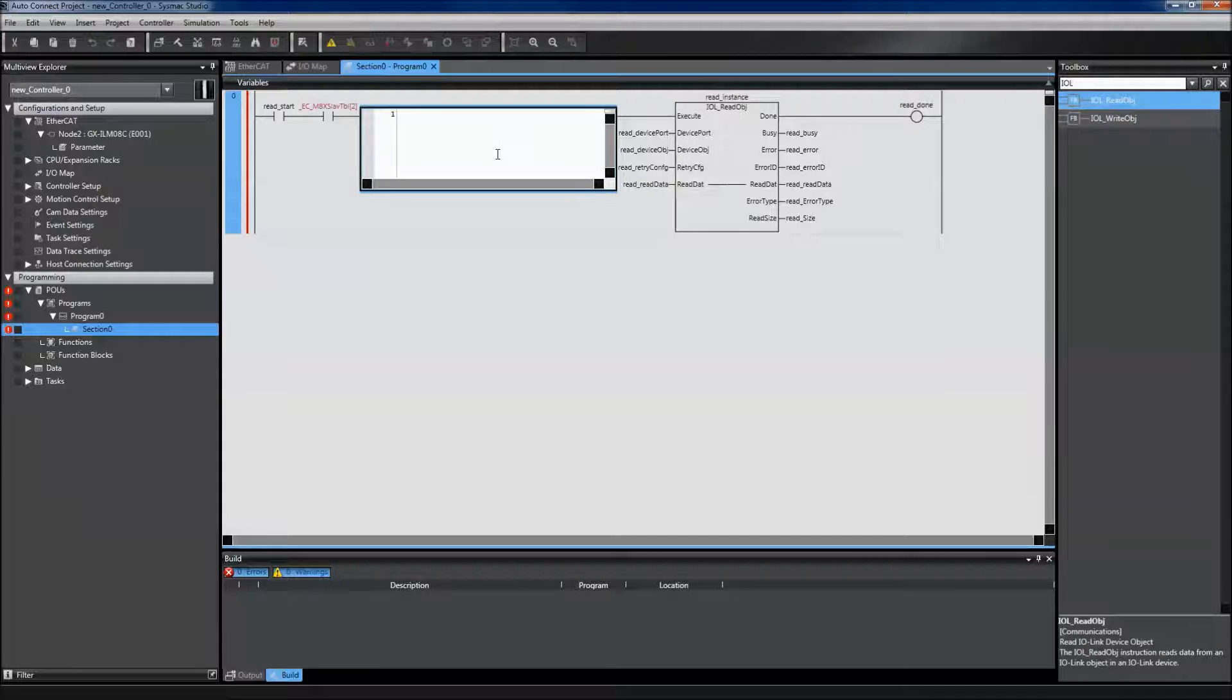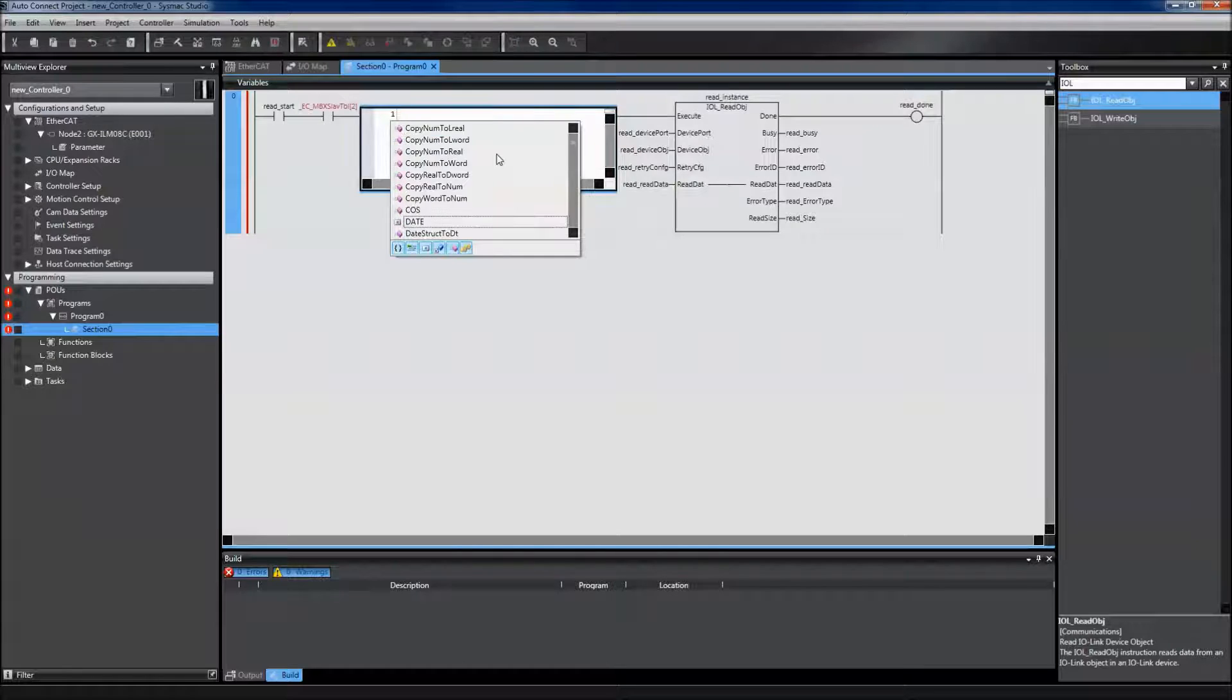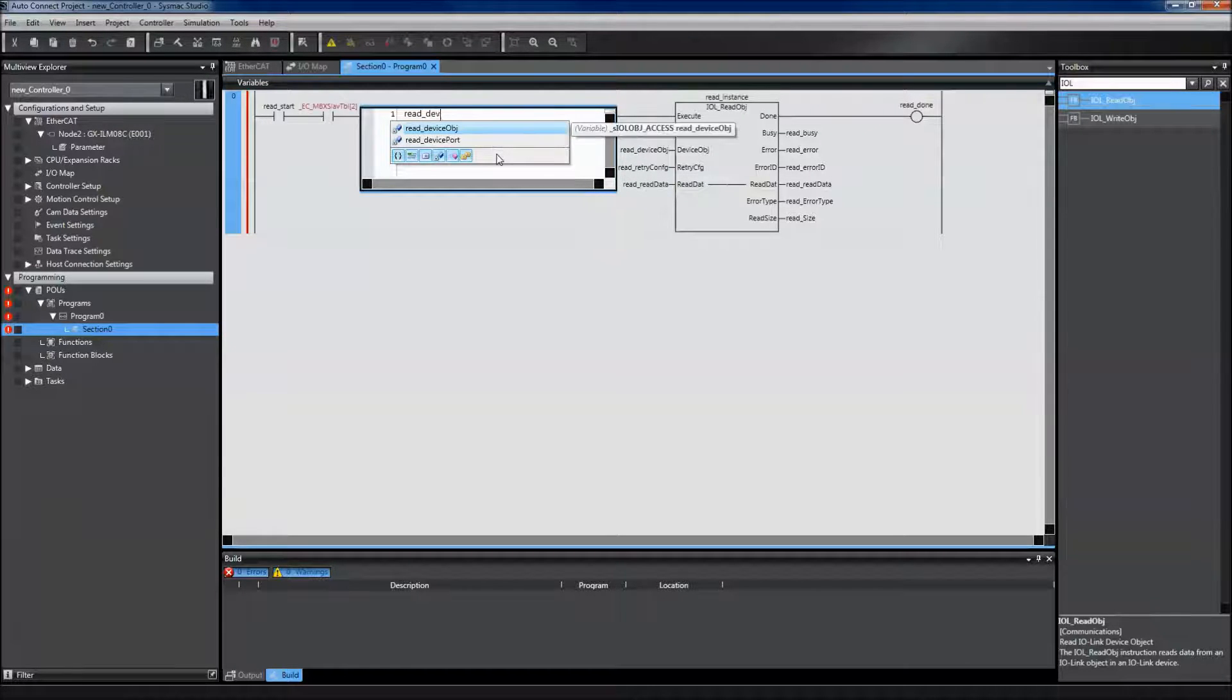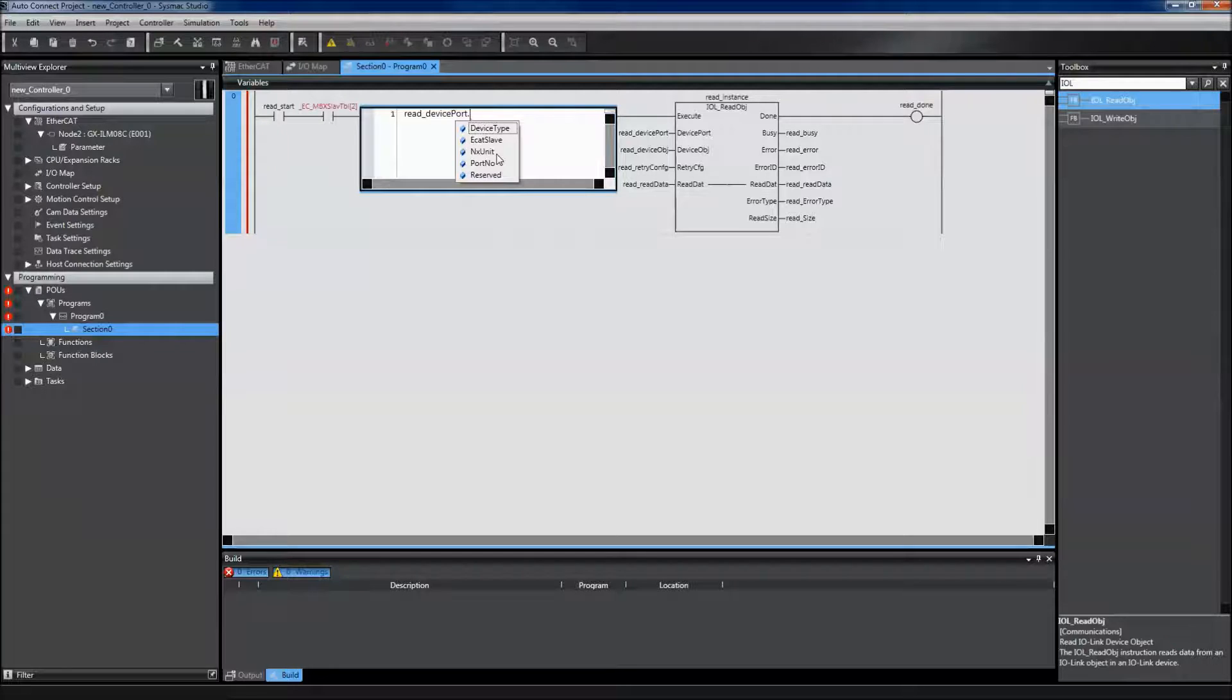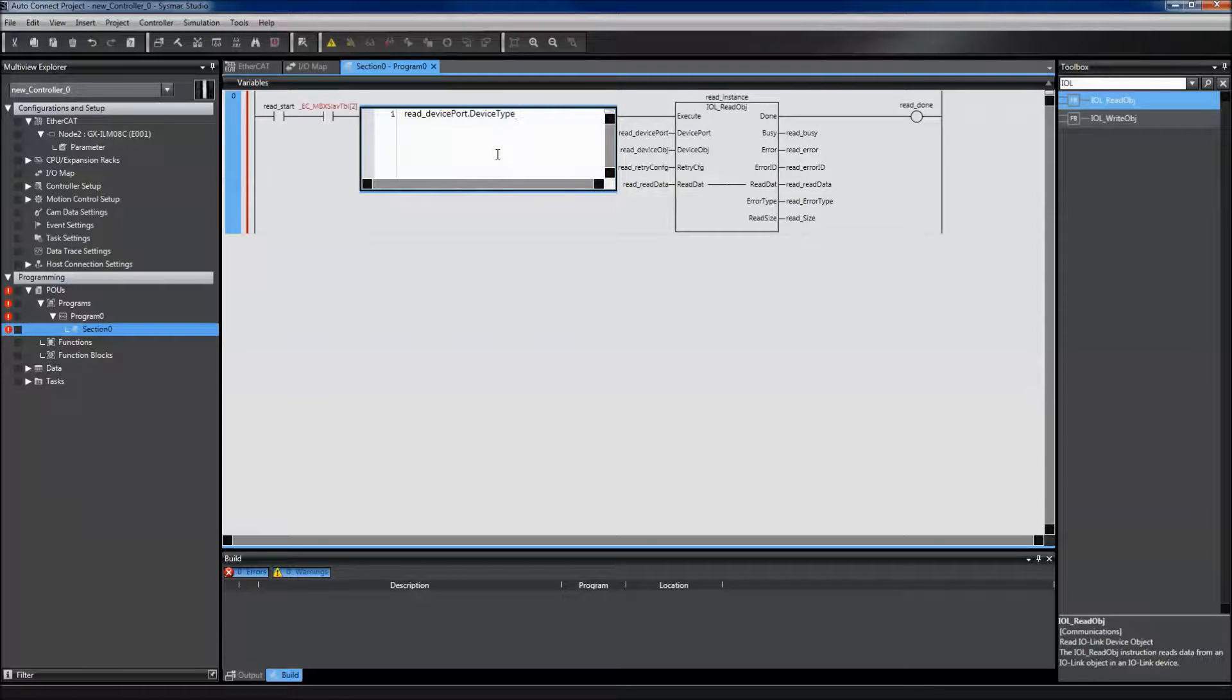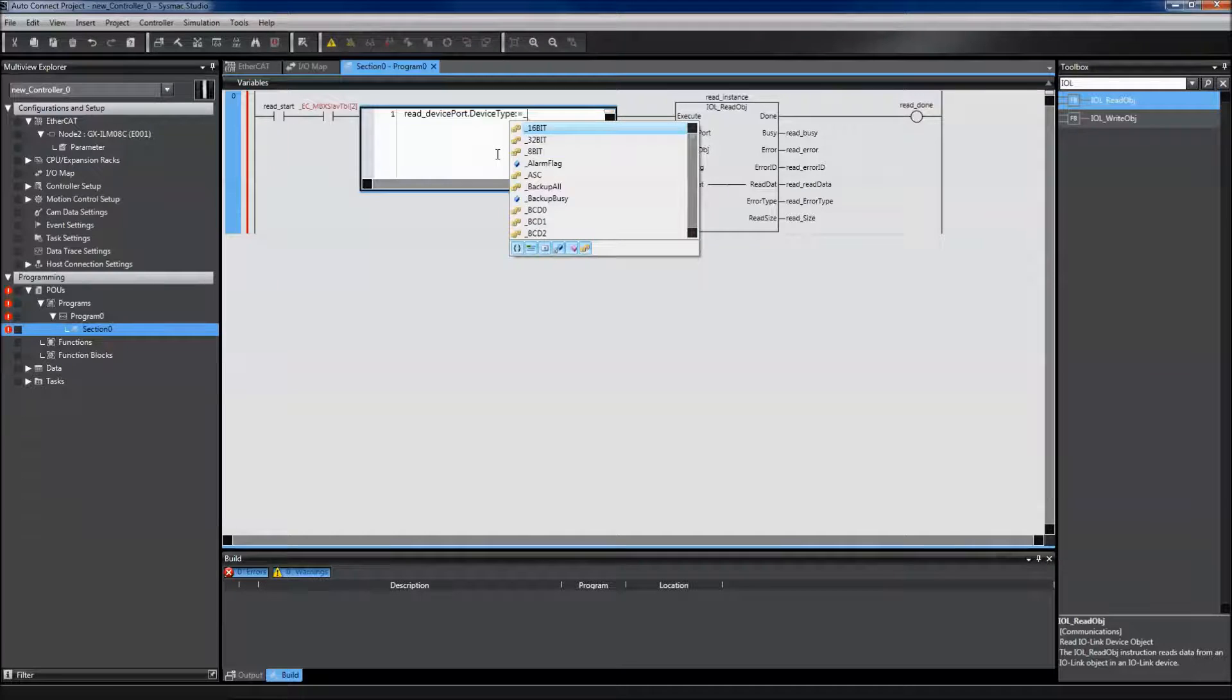The first one we need is the device type, which is under my device port. I then put a period and all of the variables under device port come up. I need to select device type. And in this instance, since I'm using the GX IO-Link Master, my device type is going to be an EtherCAT slave.